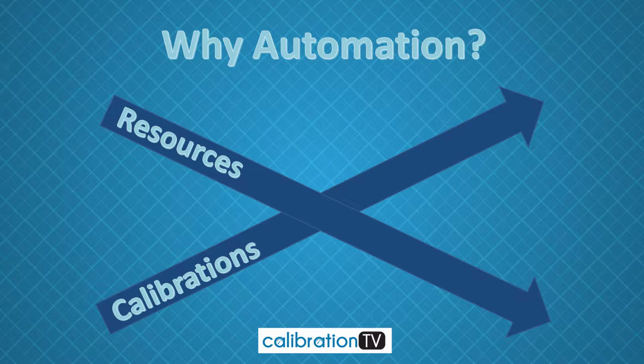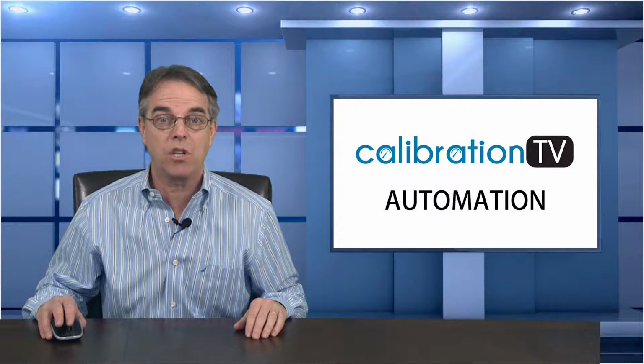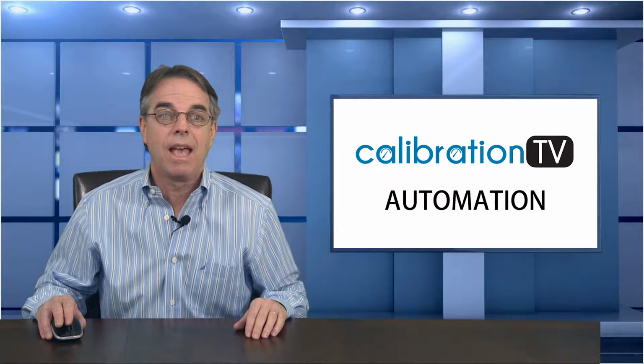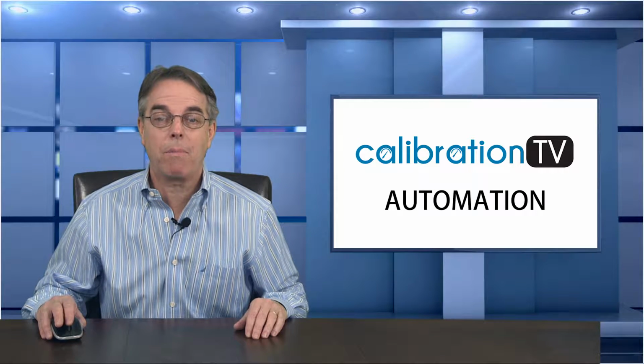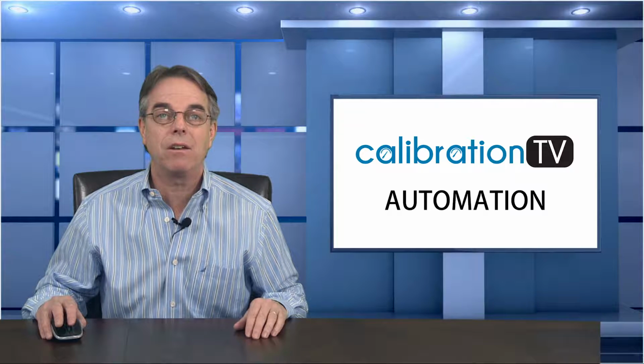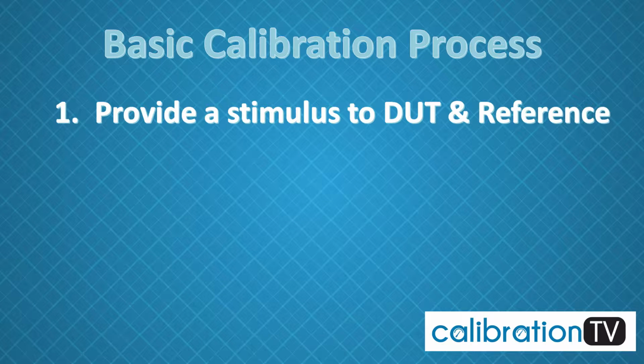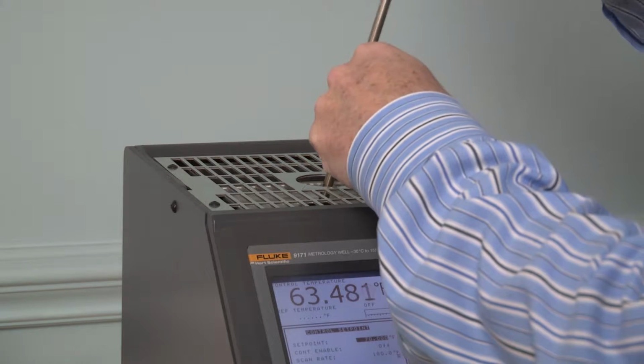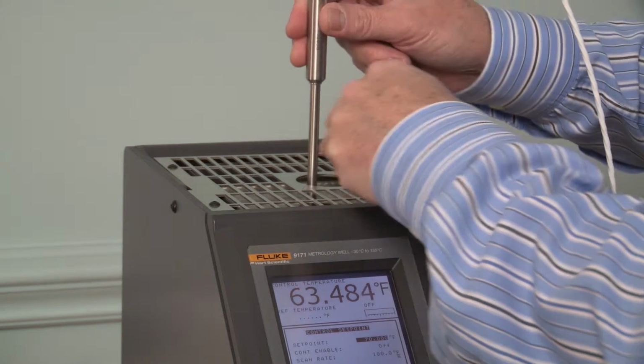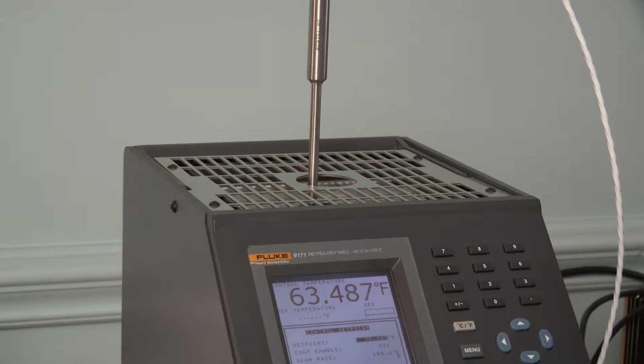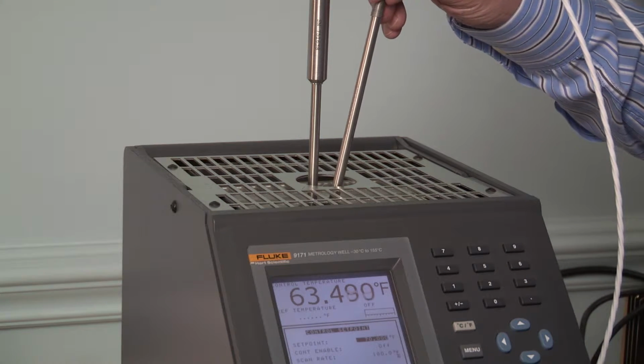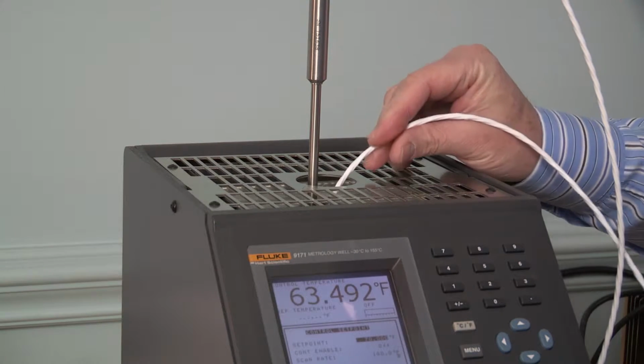In some cases, implementing some form of automated testing can be the difference between getting the work done or pushing out your calibration intervals. As most of you know, calibration is a very repetitive process, and if we had to break it down into its simplest terms, we can describe calibration this way. Number 1, provide a stimulus to the device we are testing and a reference device. Providing a stimulus for a temperature calibration, for instance, would be putting our temperature device and a reference probe in a liquid temperature bath or a dry well. We want to make sure both devices see the same stimulus, or temperature in this case.